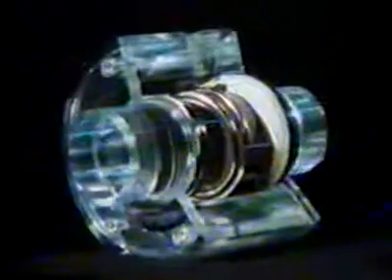Here we have it, the mechanical seal with its 5 components. Rotating seal face with secondary seal and spring. Stationary seat with secondary seal. Two rules must be observed to enable this principle to function.